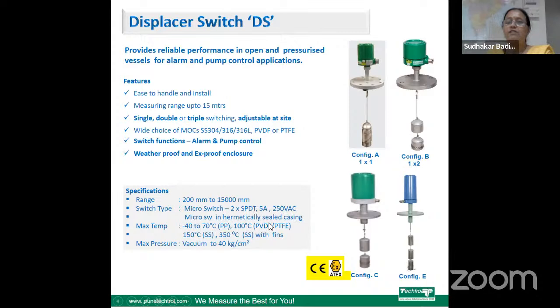Hermetically sealed casing is also available for the micro switch. It is suitable for a maximum temperature of 350 degrees Celsius and pressure of 40 kg per centimeter square. So on the right hand side, you can see the various configurations of these switches. The first one is a switch with a single displacer with a single switch. Then the second one is a level switch with split displacer and single switch, which is used for pump control application. And then 2 displacers with 2 switches and 3 displacers with 3 switching contacts.